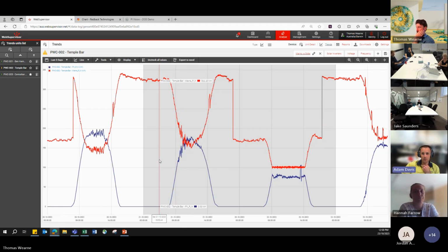And the red line here is your load, and just for anyone's interest, that's what a step change looks like. That's when a pump goes off, and that's when a pump goes on. They're big steps, and if this system could be trained to pay attention to that variable and try to respond to it when it correlates with the solar or if battery storage were added.